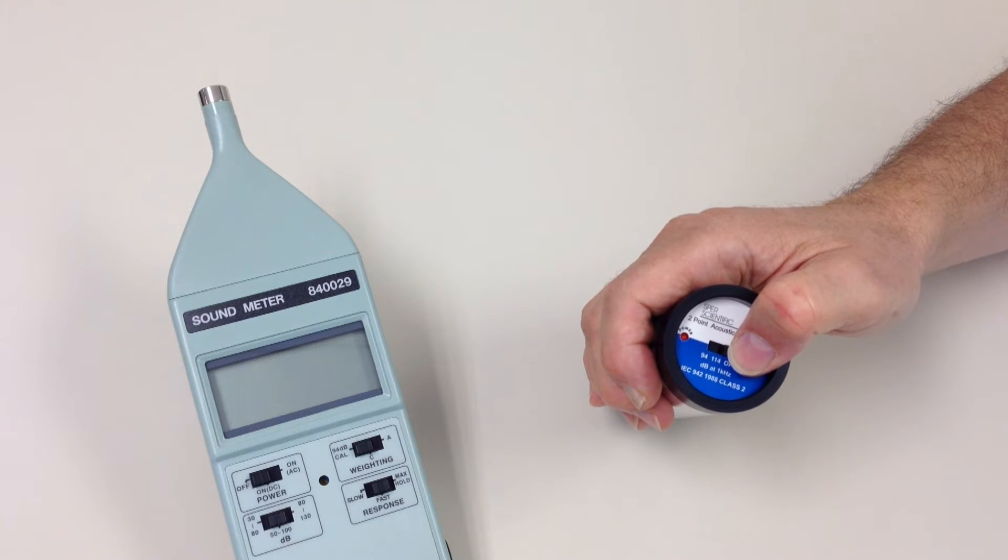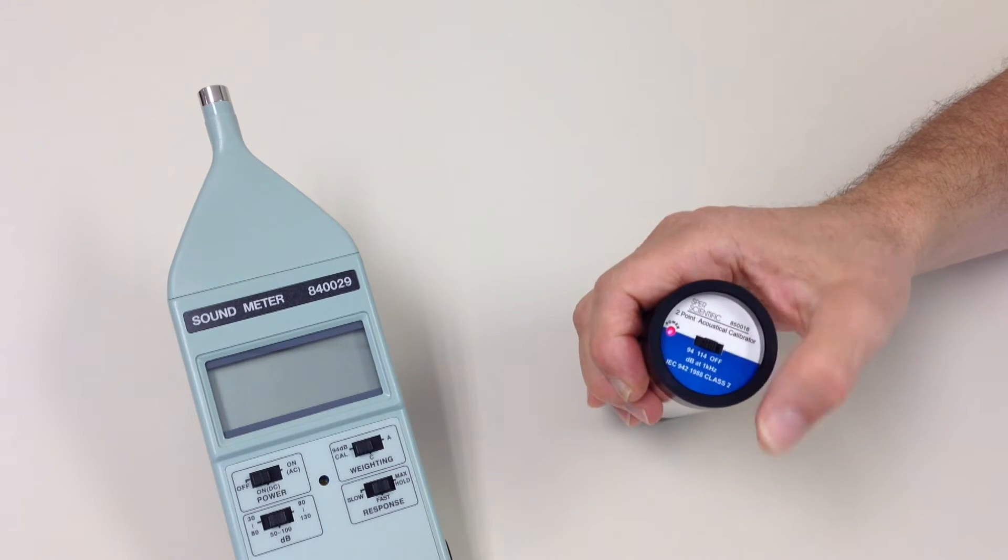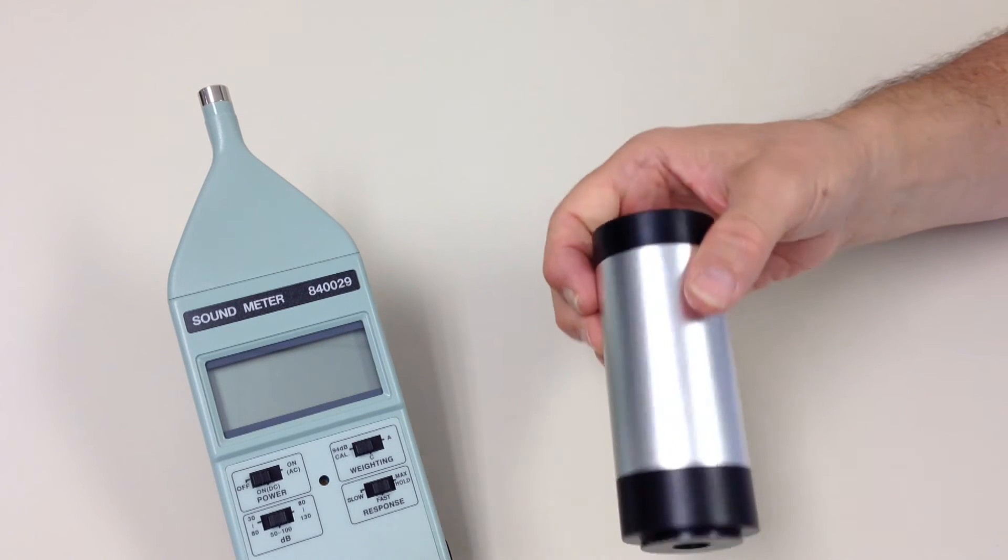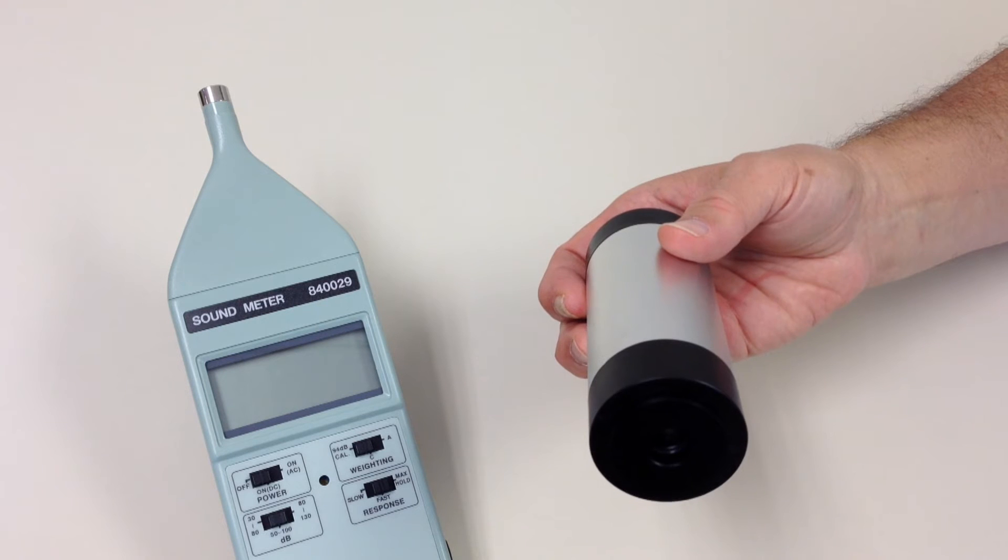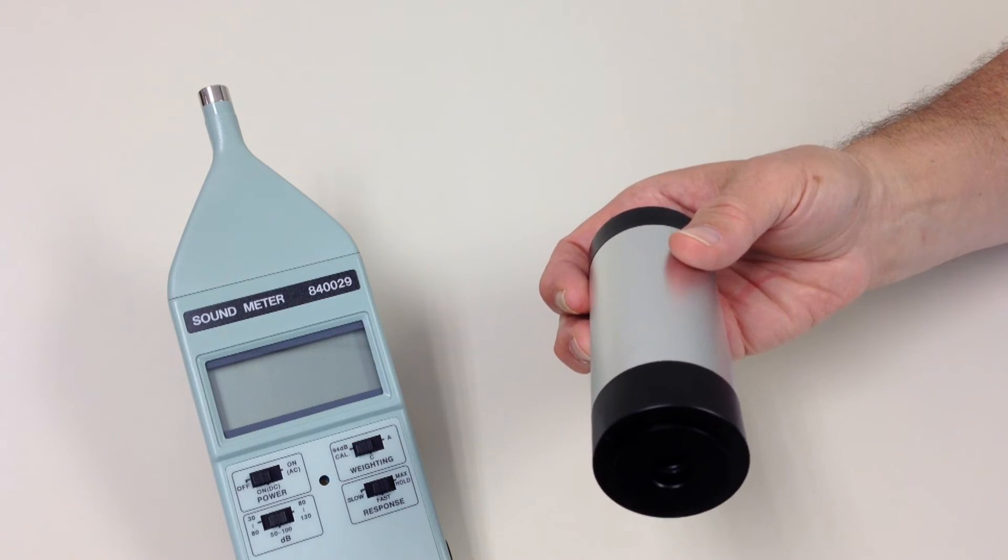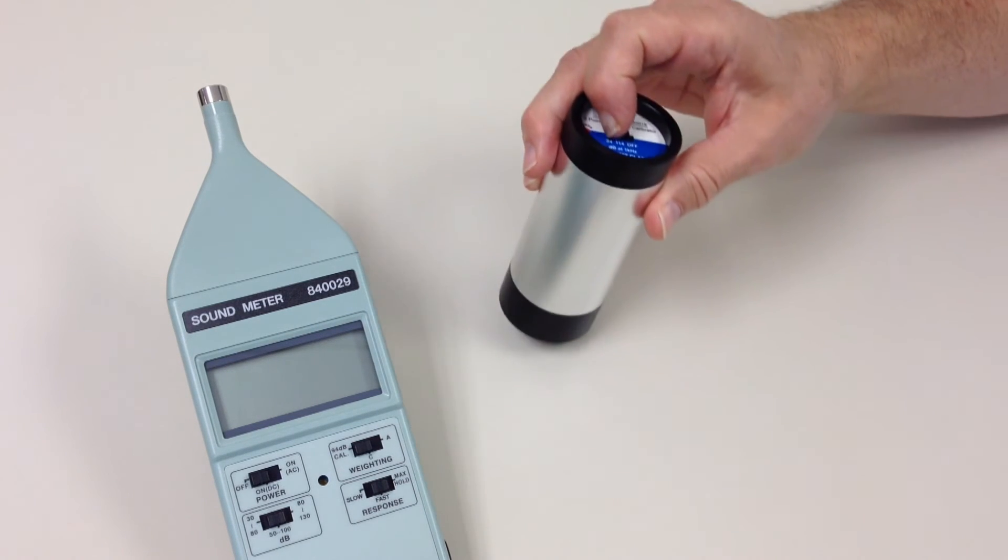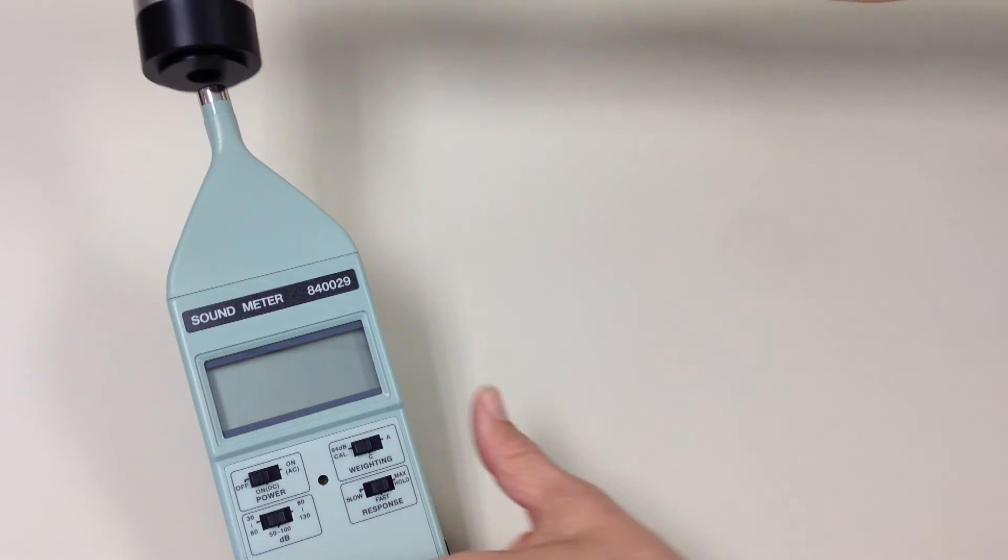To use the calibrator, turn it on and choose your calibration point, either 94 or 114 decibel. The calibrator now emits a signal at that decibel level. Next, place the calibrator over your microphone.